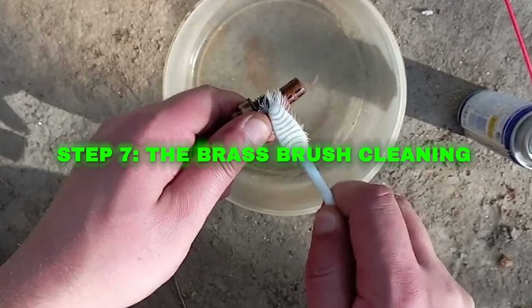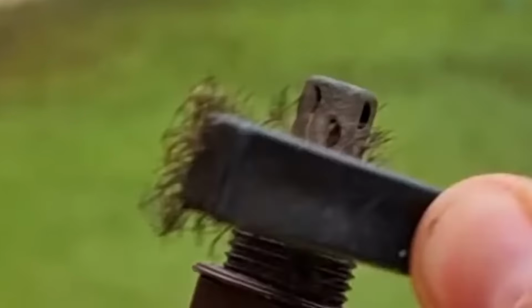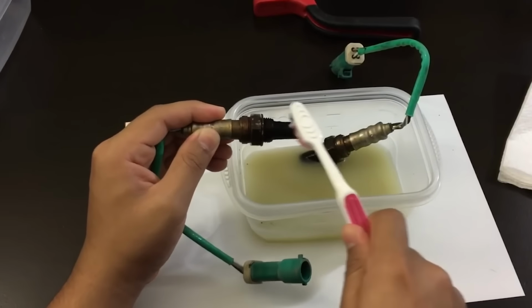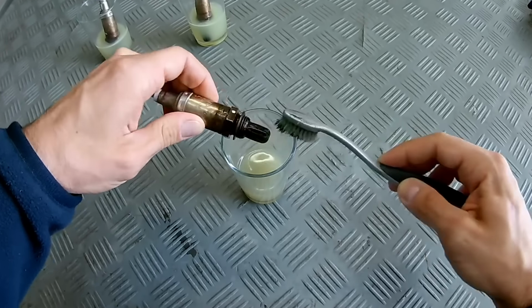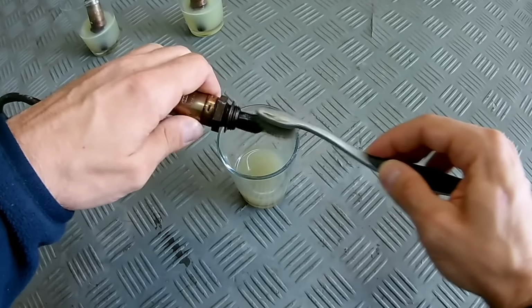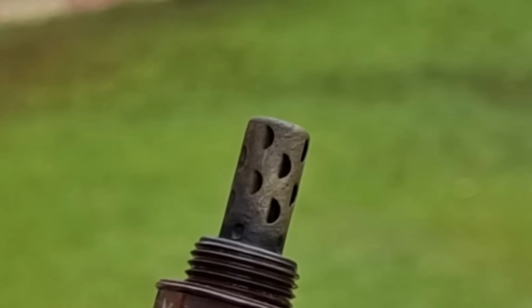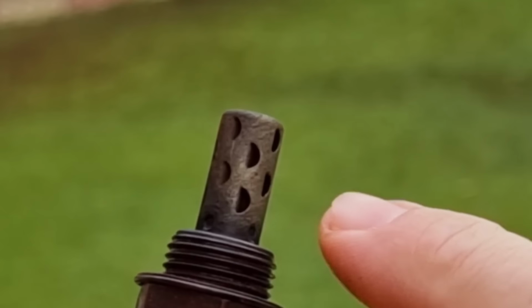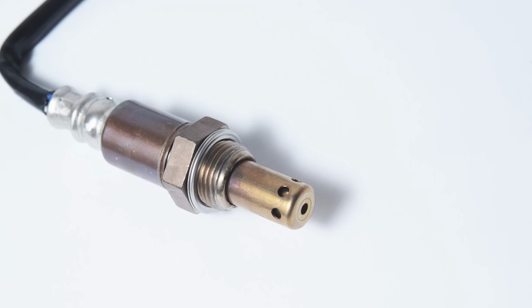Step 7. The brass brush cleaning. Using your brass wire brush, gently scrub the exterior of the sensing element. You're removing loosened deposits that the vinegar brought to the surface. Pay special attention to the small ventilation slots in the sensor housing. Clogged slots are a common cause of slow response.